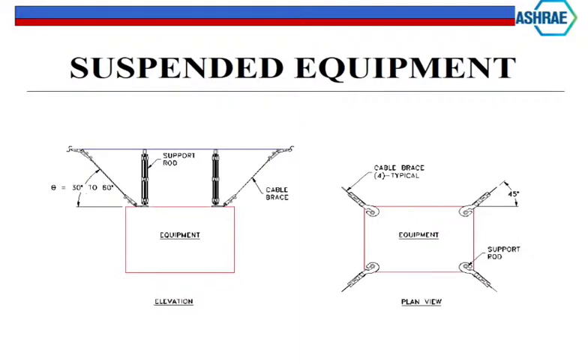So you go to equipment, and then equipment goes, okay, well, I've got a fan up in the ceiling here and so on and so forth. Okay, well, same thing. You still need to brace it. Otherwise, it's going to come down, right? In the building codes in the United States, if your fan is small enough under a certain weight and it's rigidly attached to the ductwork and that ductwork is braced, then you don't need to brace the fan itself as long as it's part of the system, right? And then every 4 years, they change that. You know, they move it to, okay, this year it's 50 pounds. Oh, next year it's 75 pounds. And then it's 50 pounds with these new caveats. You know, it just drives you crazy. They keep changing the code on us.